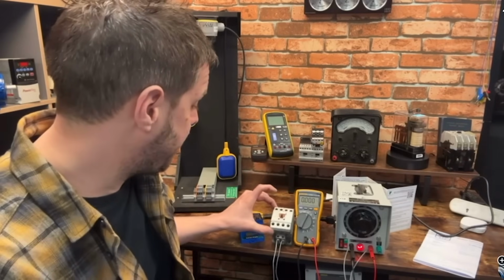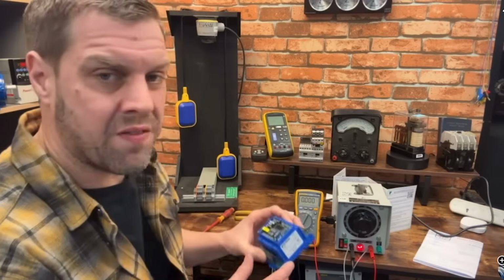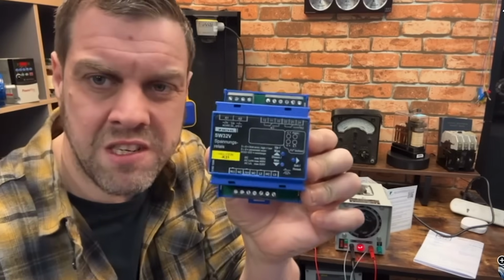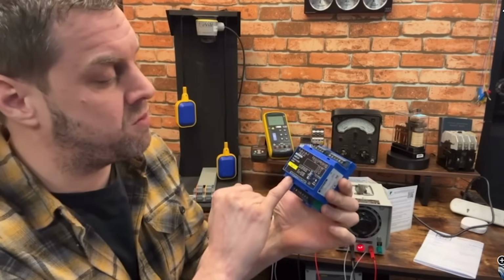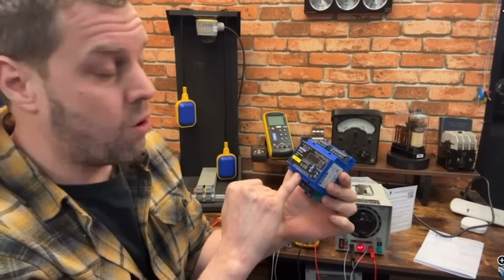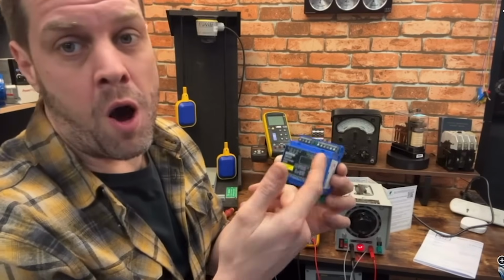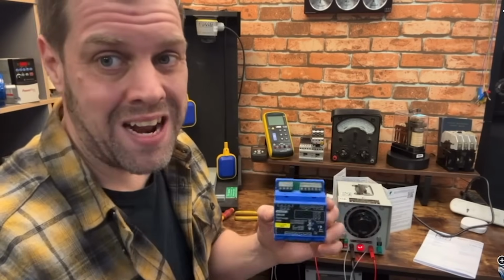I don't have a lot of 240 volt contactors because it's not my flavour, but I've gone and got one from downstairs. I've also got this voltage sensing relay to show you. You can put a voltage into it, 3 phase or single phase, whichever you want, plus a separate control voltage. You put a voltage in here and set it to operate a contact to cut out at any predetermined low point and any predetermined high point.